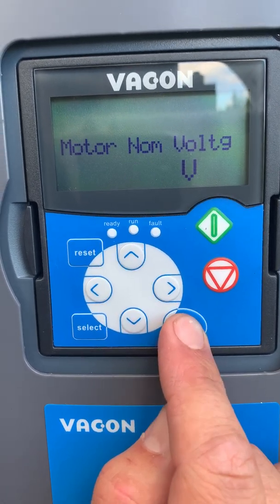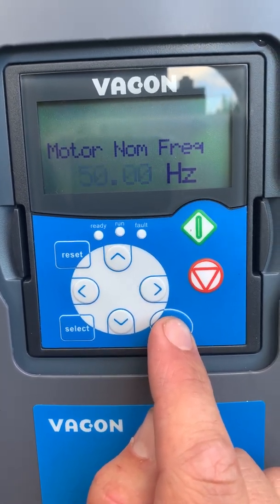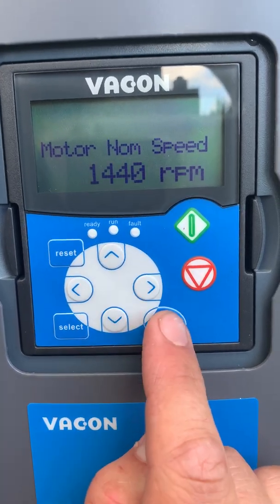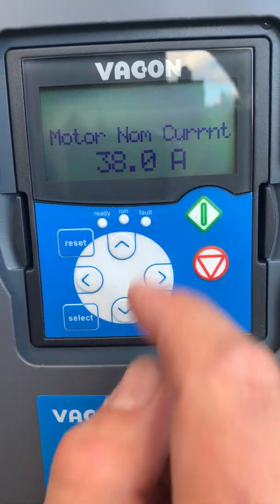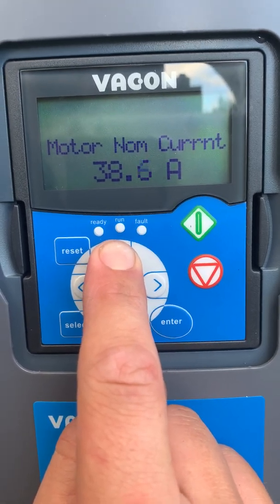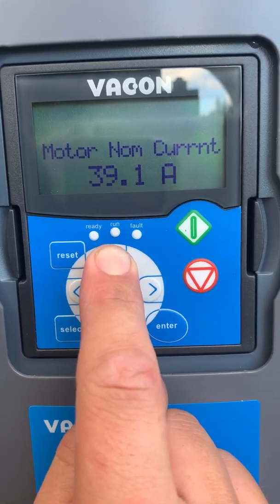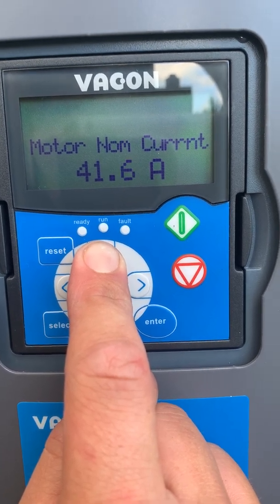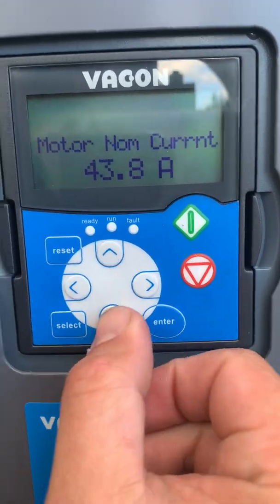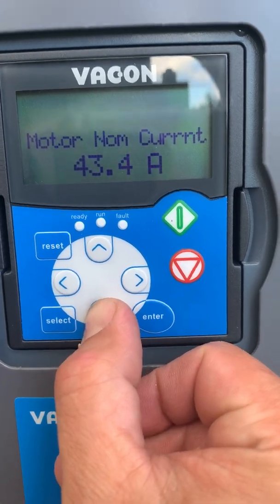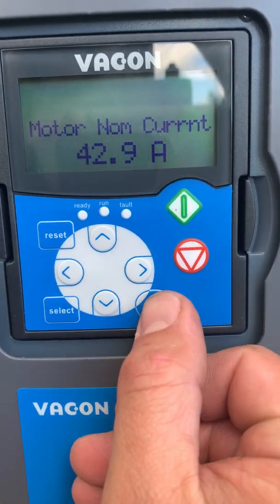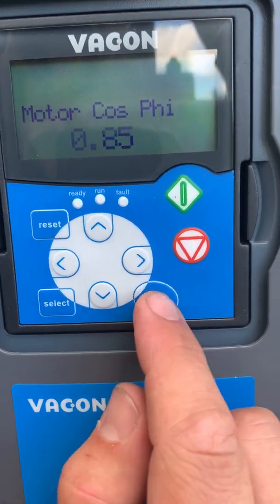Nominal voltage of the motor. Nominal frequency of the motor. Nominal speed of the motor. And the current — our compressor in this case has 43 A nominal current draw. Choose the current that's on the nameplate of your compressor. 0.85 is standard for the motor.